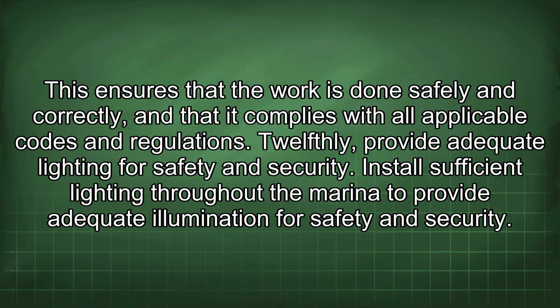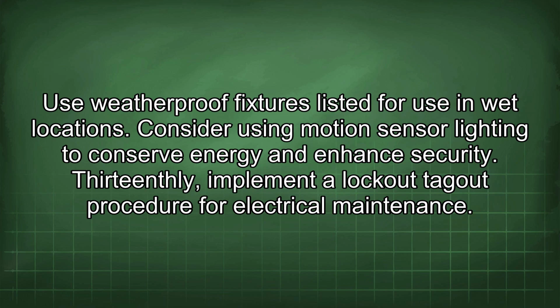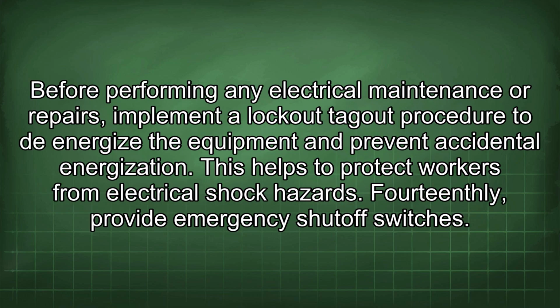Twelfthly, provide adequate lighting for safety and security. Install sufficient lighting throughout the marina to provide adequate illumination for safety and security. Use weatherproof fixtures listed for use in wet locations. Consider using motion sensor lighting to conserve energy and enhance security. Thirteenthly, implement a lockout-tagout procedure for electrical maintenance. Before performing any electrical maintenance or repairs, implement a lockout-tagout procedure to de-energize the equipment and prevent accidental energization. This helps to protect workers from electrical shock hazards. Fourteenthly, provide emergency shut-off switches.